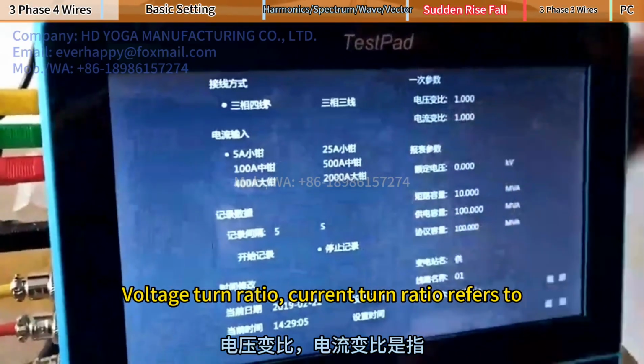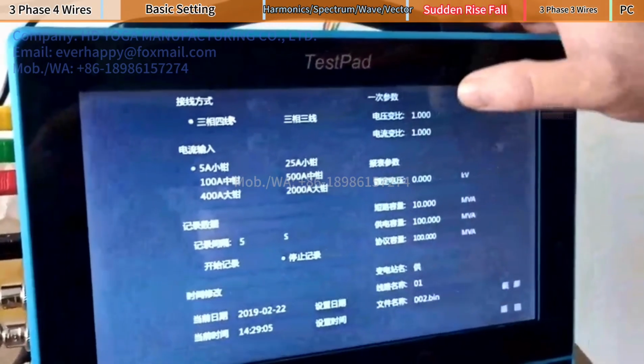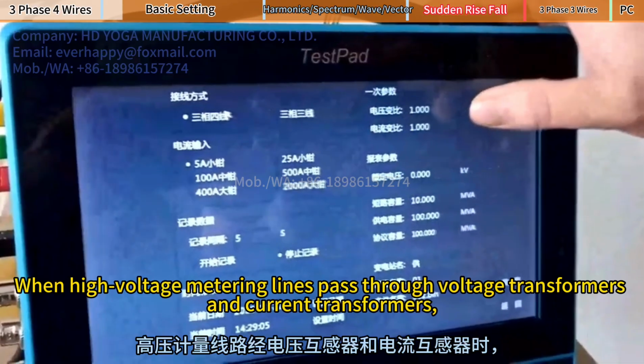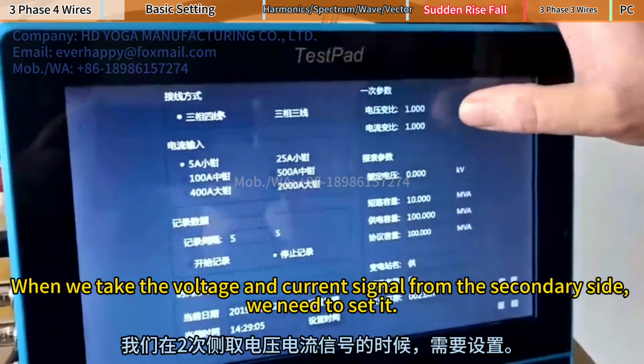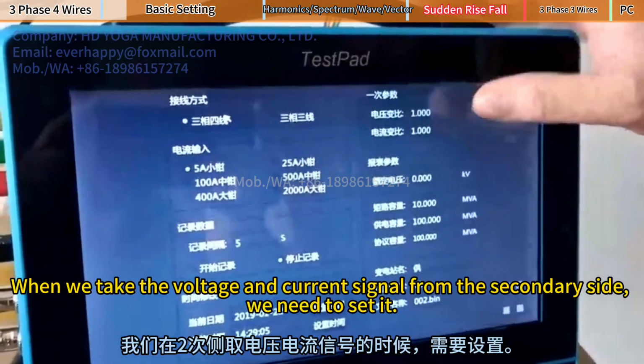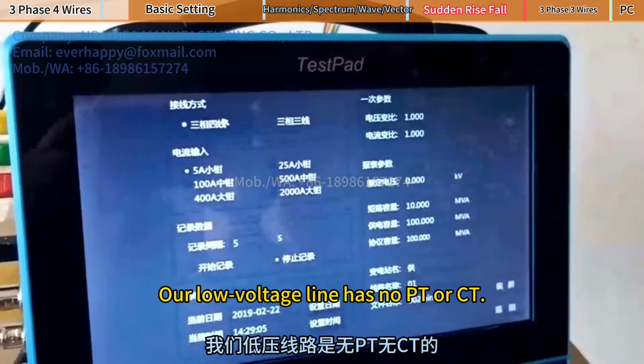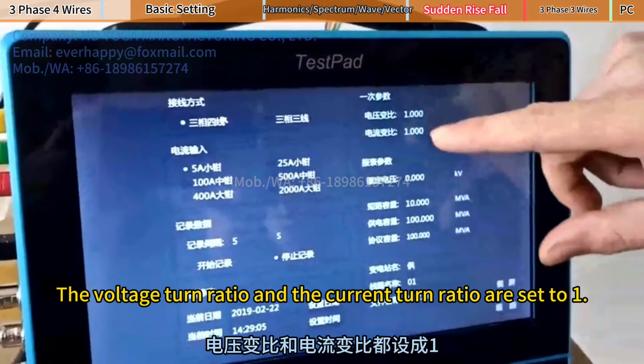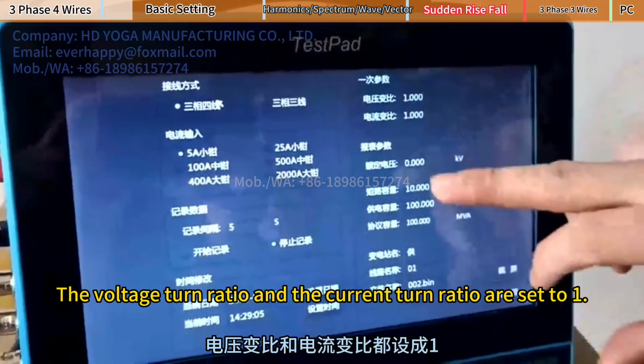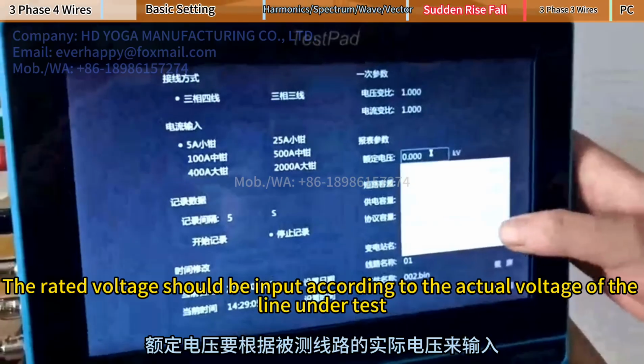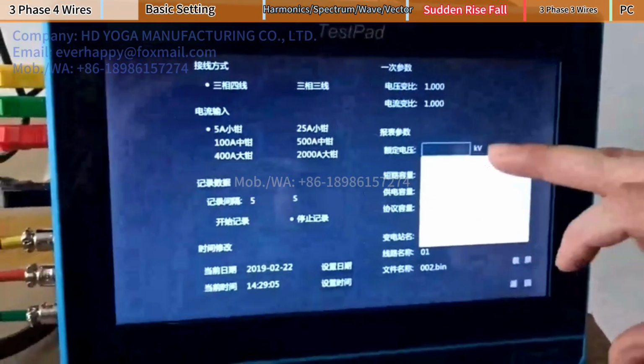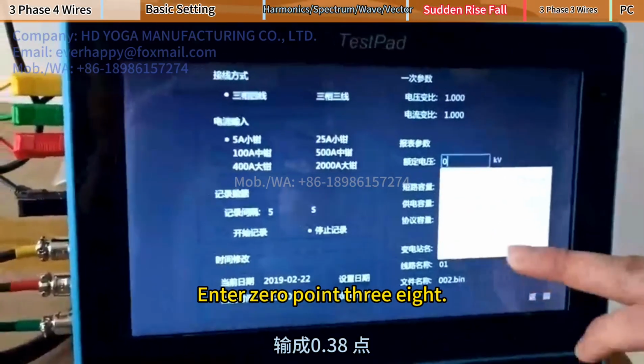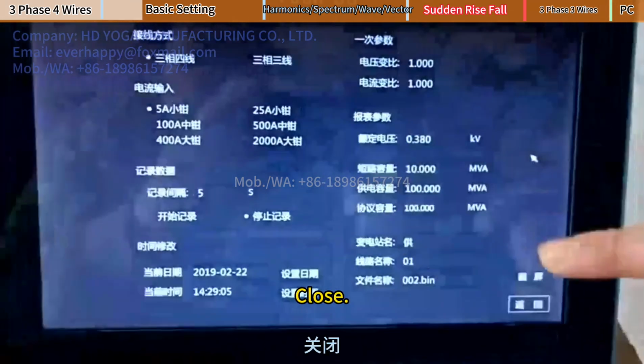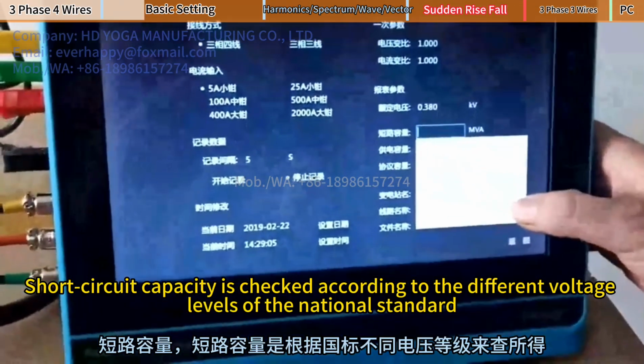Voltage turn ratio, current turn ratio: these refer to when high voltage metering lines pass through voltage transformers and current transformers. When we take the voltage and current signal from the secondary side, we need to set it. Our low voltage line has no PT or CT, so the voltage turn ratio and the current turn ratio are set to 1. The rated voltage should be input according to the actual voltage of the line under test. We are 380 volts. Note that the unit is kilovolts. Enter 0.38. Close.